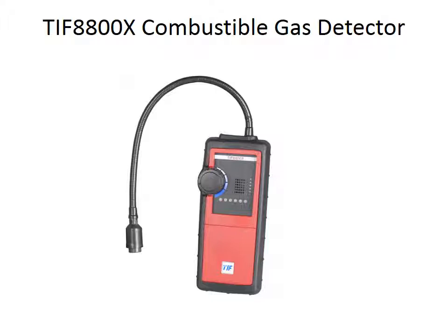It just works simply, it has the sensor for combustible gas. It's not going to give you a percentage LEL. It's just going to help you locate that leak. The way this works, on the top where you see that little probe coming out of the device, there's an on button. You push it to turn it on. The selector knob on the left side of the unit, you want to start all the way counterclockwise. Turn it on.